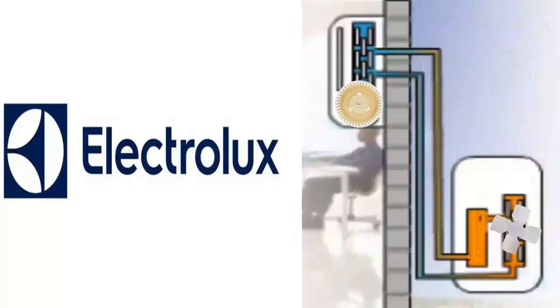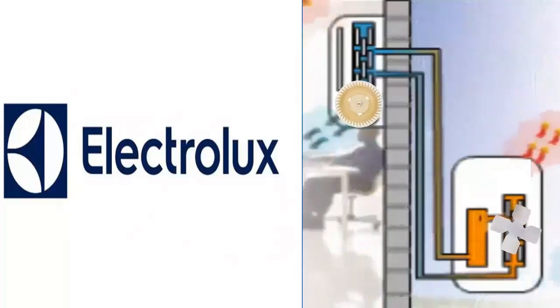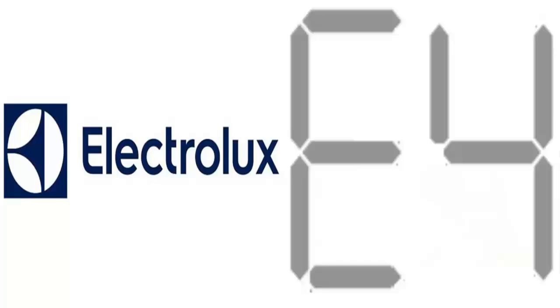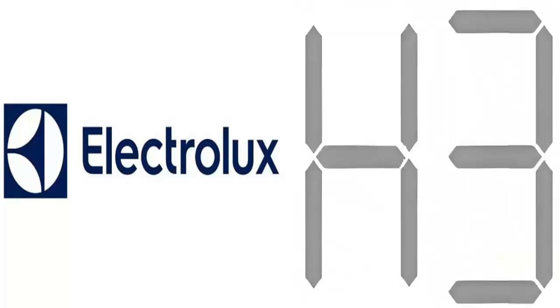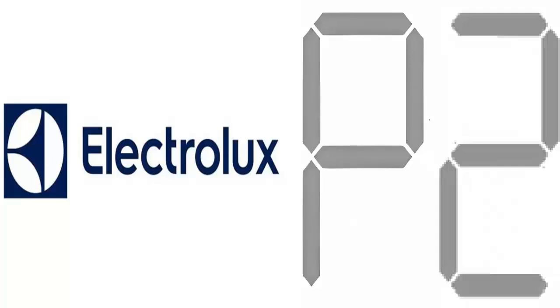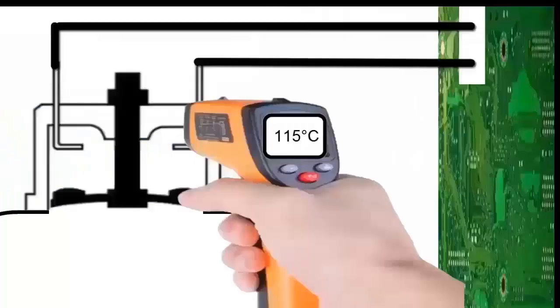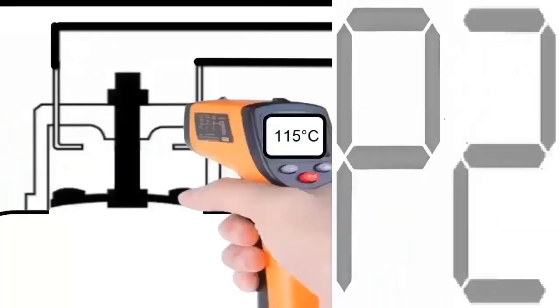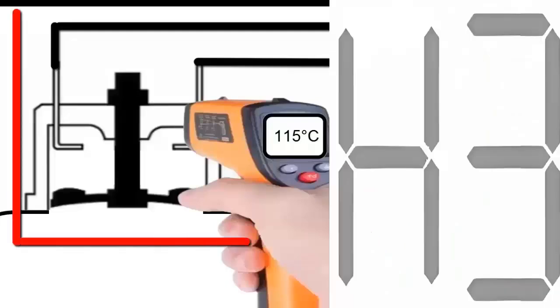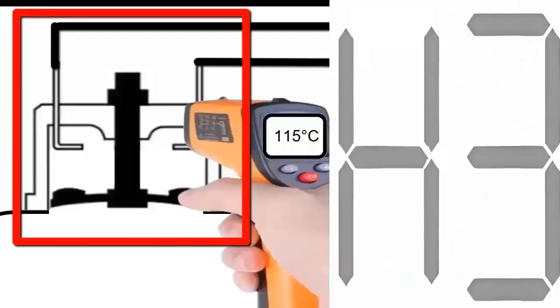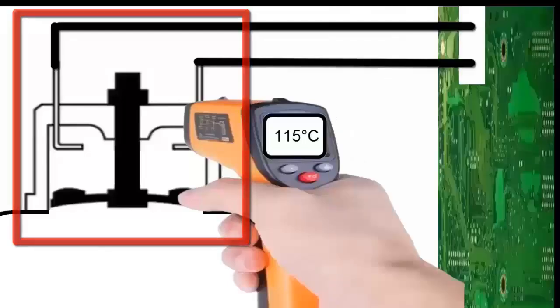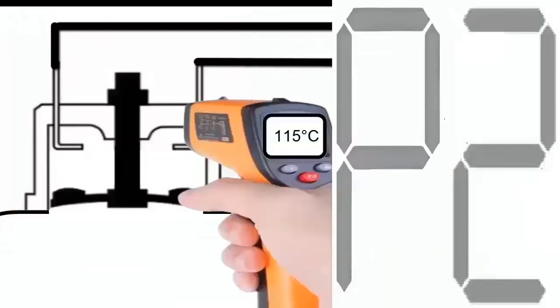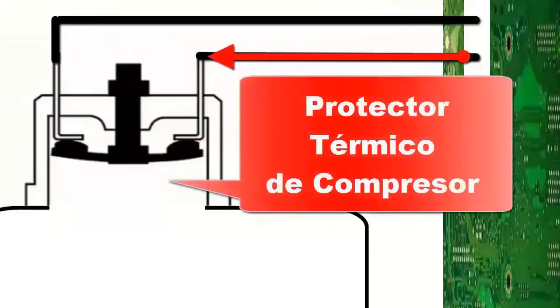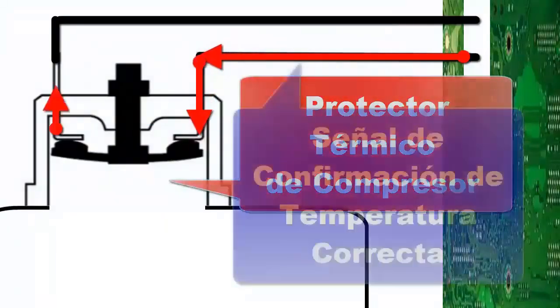In this video, we explore the faults and error codes of Electrolux air conditioners related to compressor issues. For Electrolux, the error codes E4, H3, and P2 are protections that activate when an overload is detected in the compressor. This problem manifests when the temperature switch located on top of the compressor sends a signal to the electronic control module of the external unit due to measuring a higher than normal temperature at the compressor head.